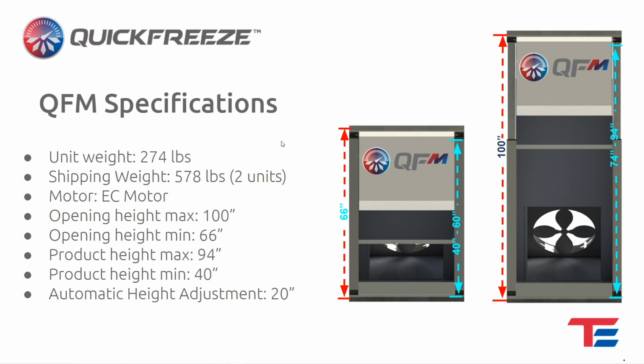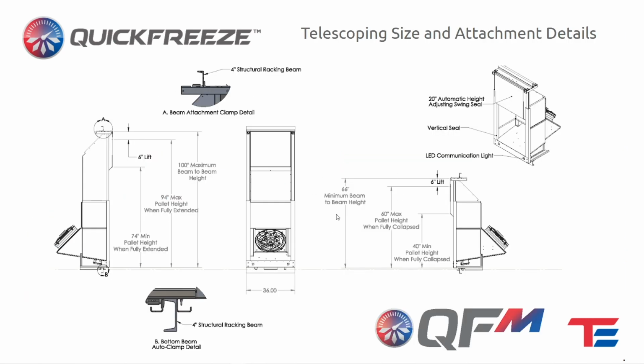Here's some specifications on the unit. They're 274 pounds, so typically structural racking is rated at 2,500 or 3,000 pounds per position, so that's not an issue with the weight of the unit. And then the units have the EC motor, which are daisy chained between each other. So you'd start out with an outlet, and then the units plug one into the next, up to 20 units on a 25 amp circuit.